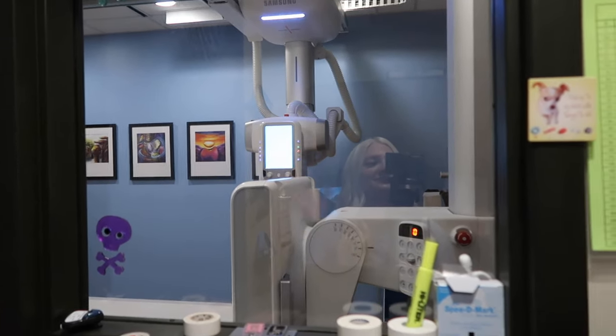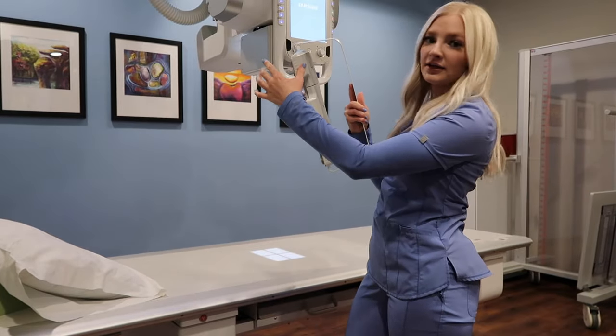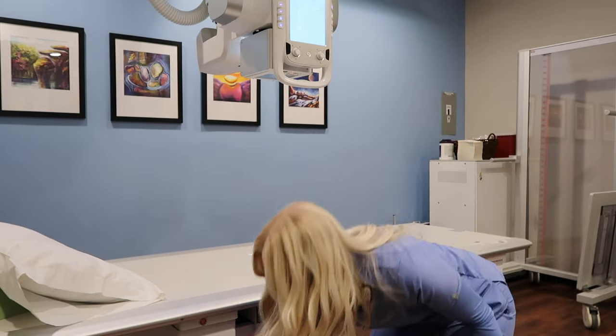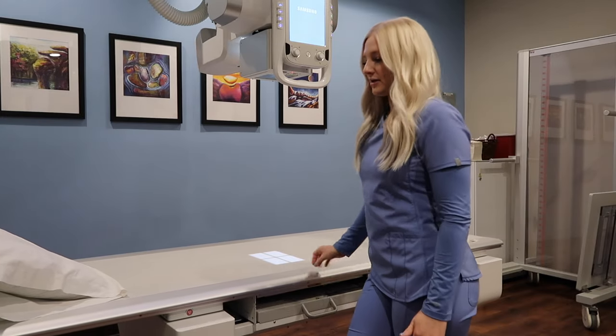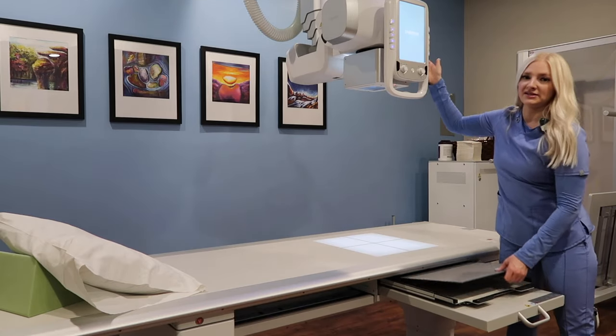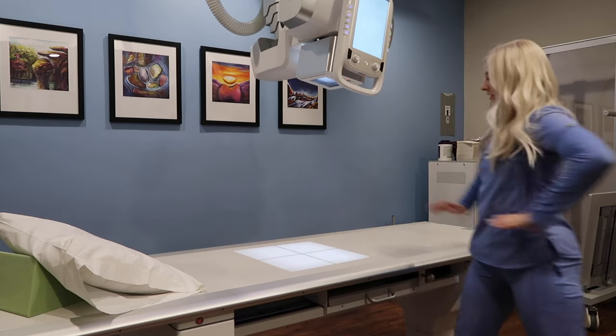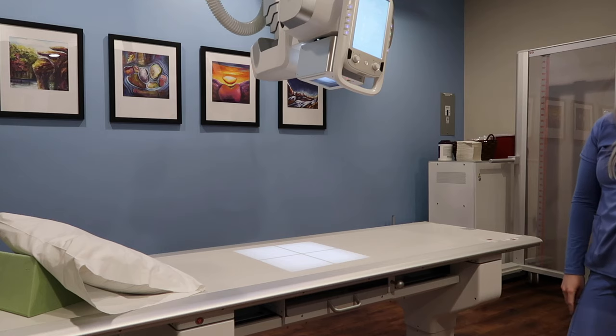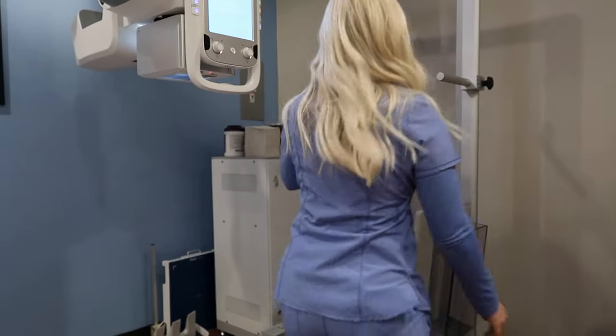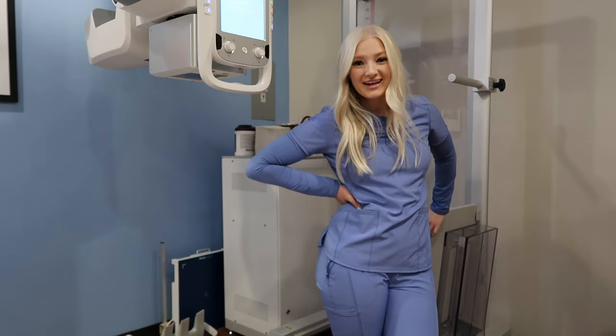This is the actual X-ray area where you'd expose — this is the exposure switch. This is the X-ray table. There is a foot pedal where you can send the table down or up. The free-floating button unlocks it in all ways so you can float the patient around. The detector is here — we have a 14x17. If I'm doing a knee and throwing a little angle on, sometimes it won't move and I'd have to hit the bucky button to center it. This big tall unit over here is what we use to do weight-bearing feet and scoliosis exams.